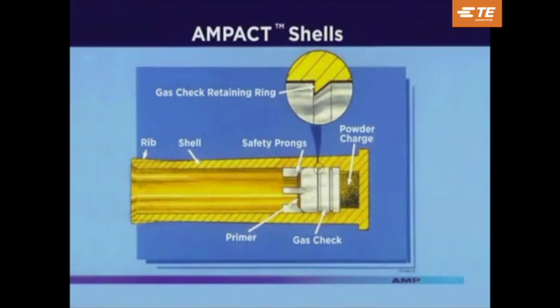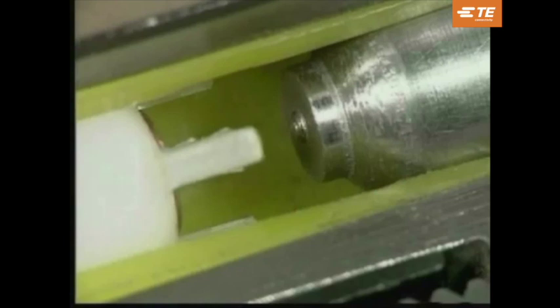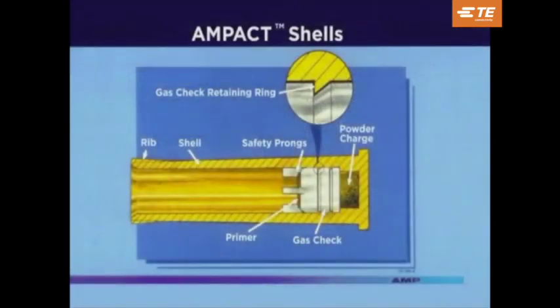This cutaway of the shell will help you better understand its operation. The shell casing is a polyethylene plastic, which contains a retaining ring for the gas check. The primer and powder charge are standard shotgun primer and powder. The safety prongs isolate the firing pin from the primer until it is collapsed by tightening the tool onto the tap. These shells cannot be used in any type of firearm, and the Ampact tool will not accept any other type.